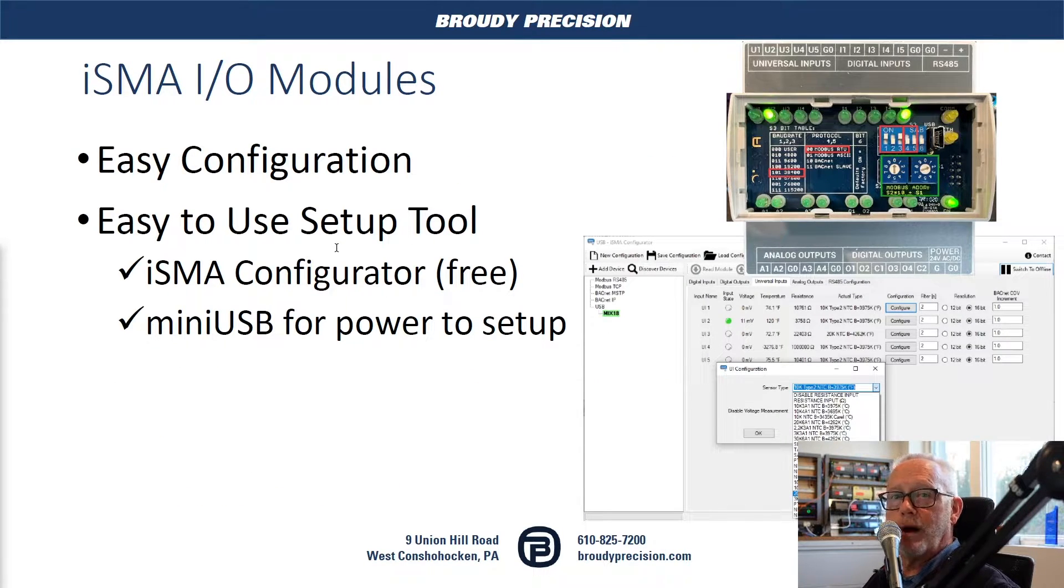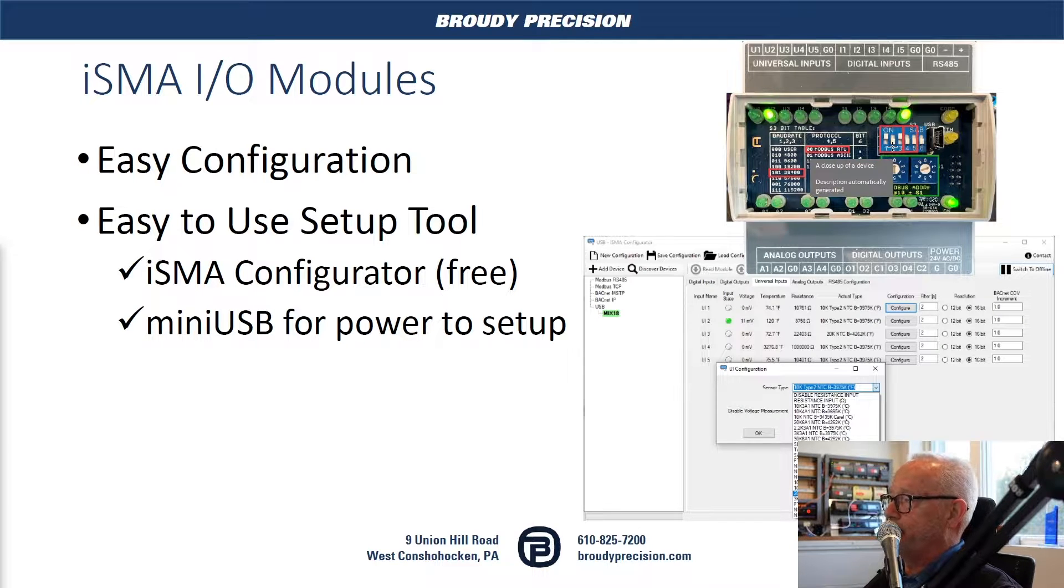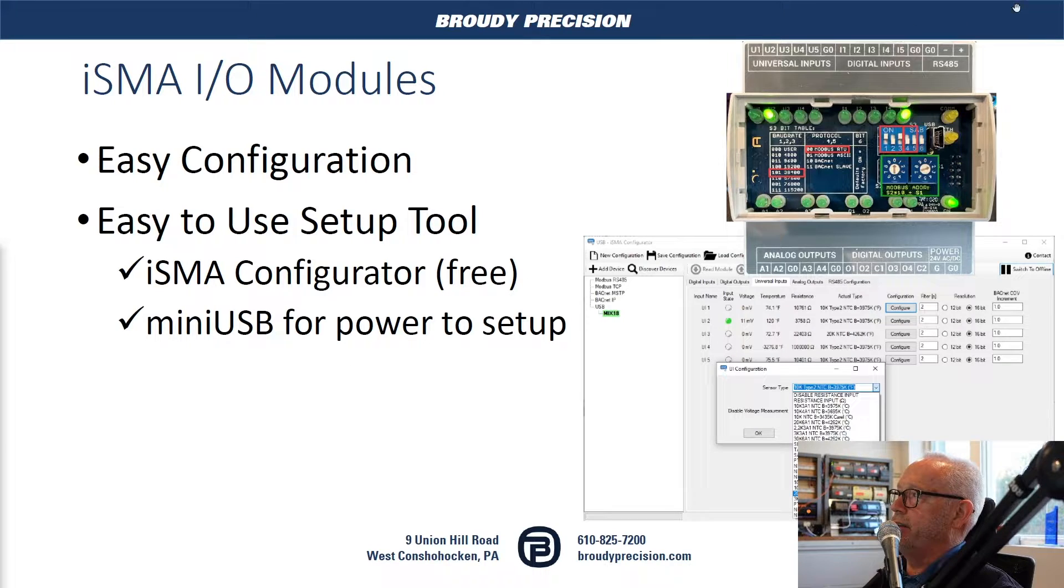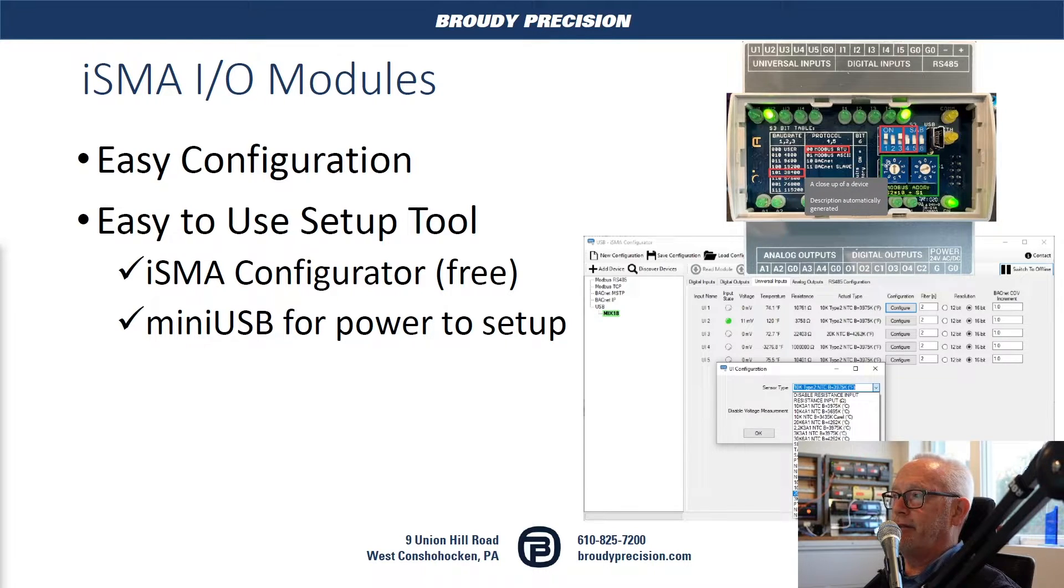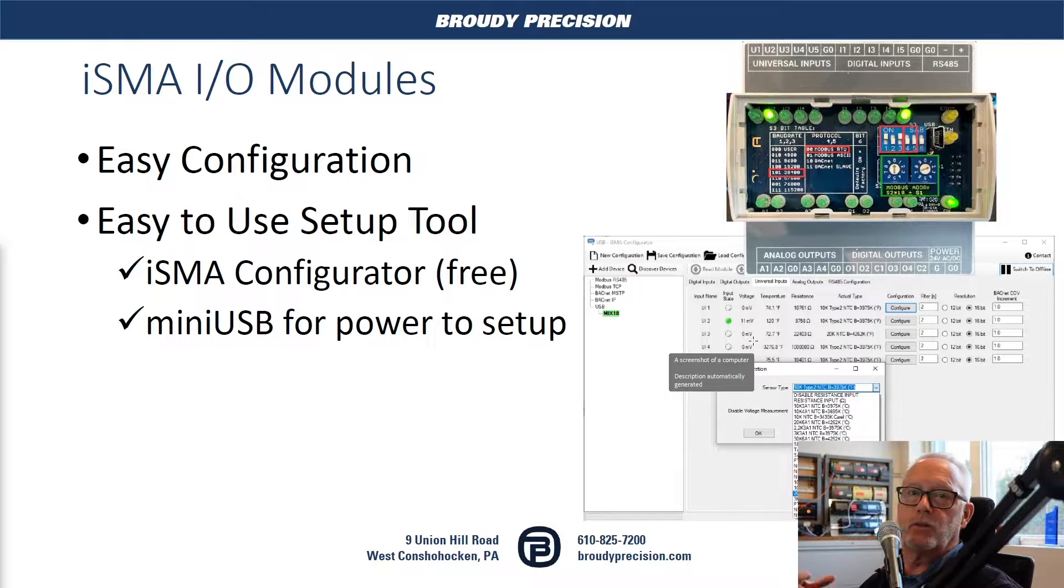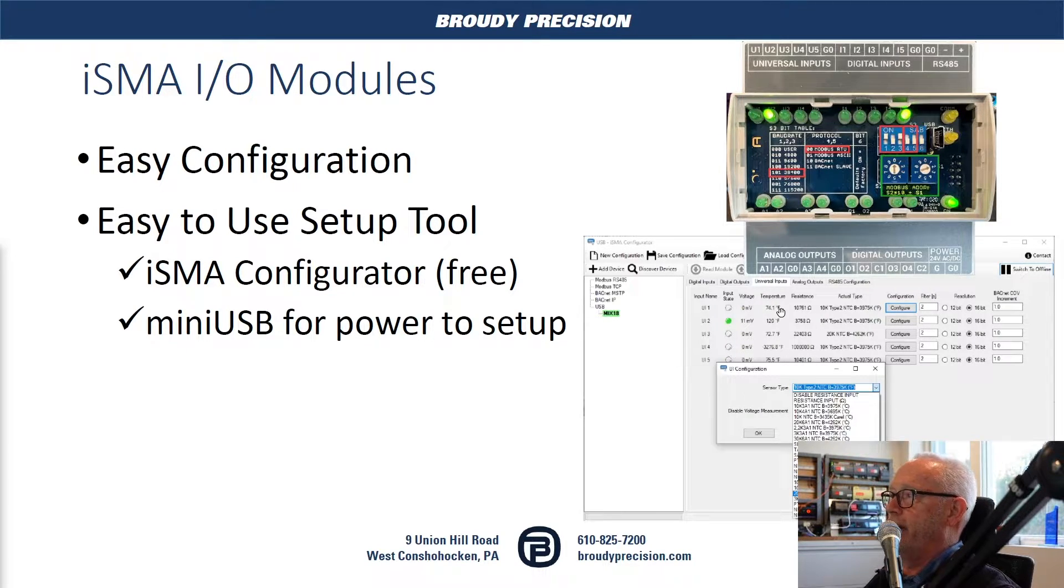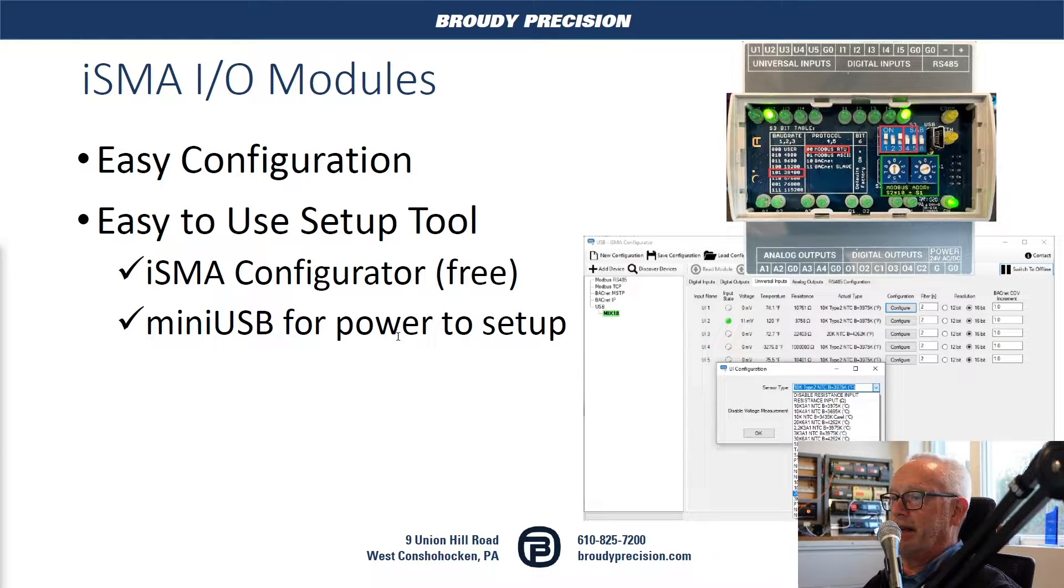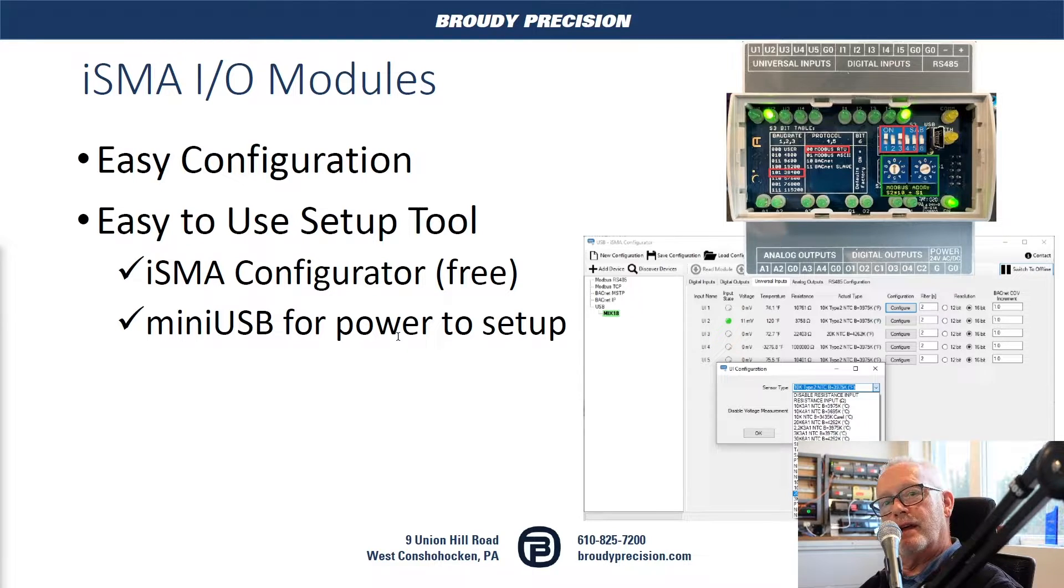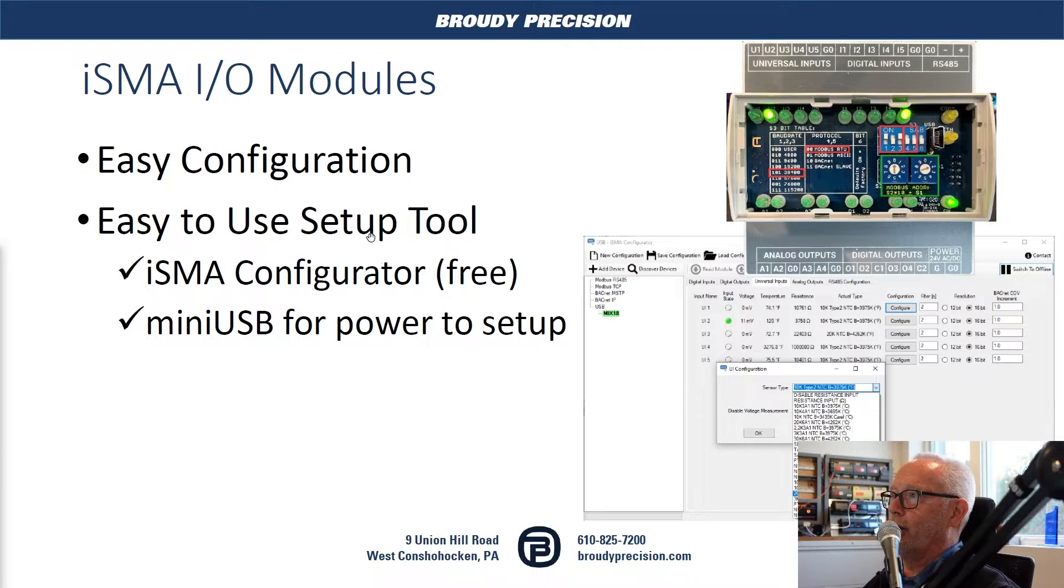On the ISMA control modules or these I/O modules, they're very easy to configure. You can see it's dip switch selectable for the baud rate and the protocol, and then there's rotary switches to do your Modbus addressing. One of the nice things about this product is if you connect through their mini USB port, that will power the device. They have a free configurator tool that you can use to configure your inputs and outputs. You can wire it up and power it up with normal 24-volt AC or DC and then bring it into your controller.